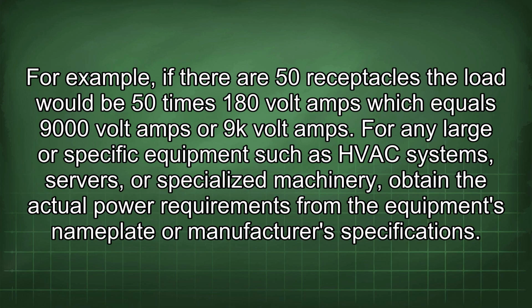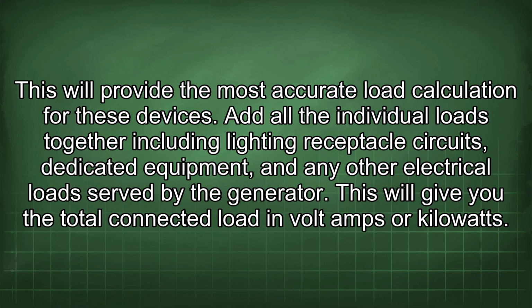For any large or specific equipment such as HVAC systems, servers, or specialized machinery, obtain the actual power requirements from the equipment's nameplate or manufacturer's specifications. This will provide the most accurate load calculation for these devices. Add all the individual loads together, including lighting, receptacle circuits, dedicated equipment, and any other electrical load served by the generator. This will give you the total connected load in volt amps or kilowatts.